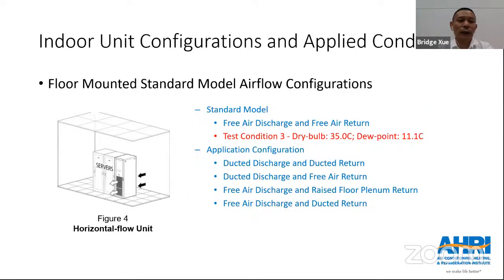And then the configuration for the horizontal flow unit. It's not common today. You can see here the standard model will be free air discharge and free air return, and the temperature is much higher. The dry bulb will be up to 35 degrees C. The dew point is the same. They also have four different application configurations. The first is ducted discharge and ducted return. The second is ducted discharge and free air return. The third is free air discharge and raised floor plenum return. And the last one is free air discharge and ducted return.